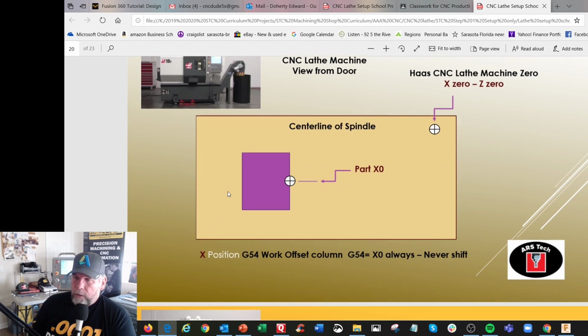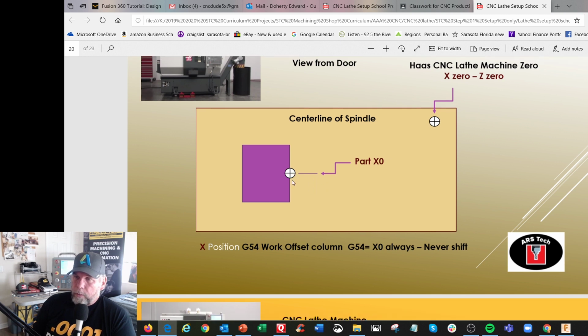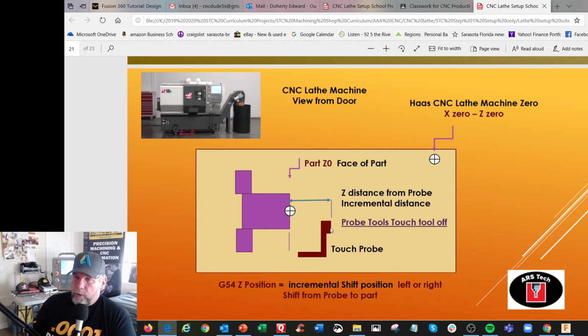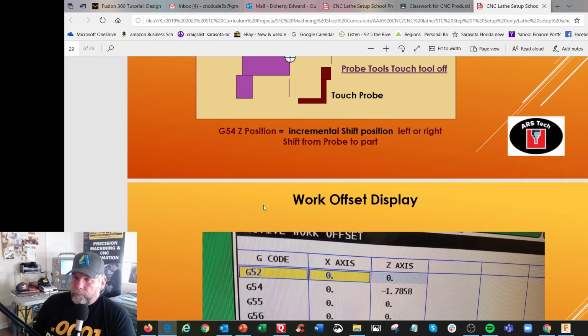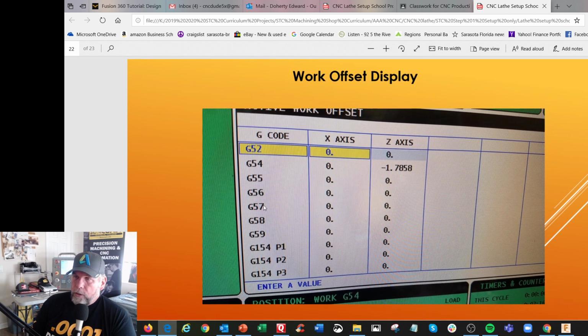all right. So here the X is always 0. Never shift the X, and wherever the part is compared to the probe. So if the probe is here and the part is here, you've got to get this distance in here. You've got to figure that out, so you're incrementally shifting it left or right, most likely left, unless you have a very long part. All right, so in this column here, you're not going to have anything. You're just going to have a shift in the Z-axis.